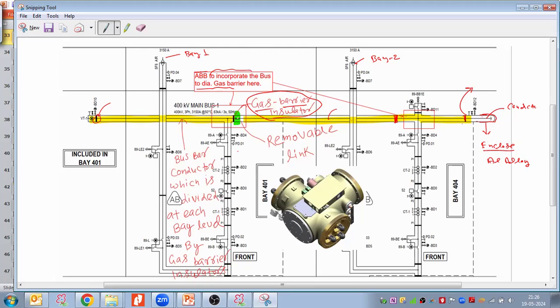Now if you see here, they are taking the bus disconnector and the earthing switch, which is part of the bus bar modules, then one insulator over here. This breaker has CT on both sides. So from here to here one module, here to here one breaker module, from here to here CTA CTB module. Then from here to here again the line disconnectors and their modules, and then it is taking out. Then here again we have line disconnectors and earthing switch, so this module here. Then this one is the high speed earthing switch, and then here it is going outside.